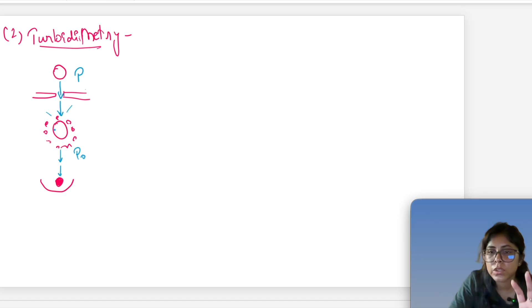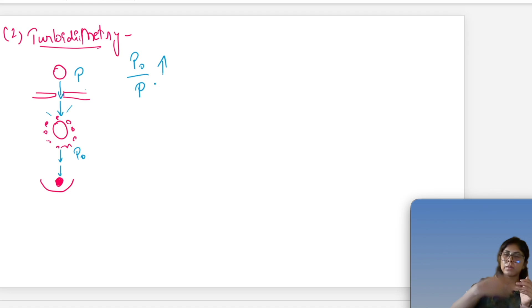If more light is coming out, that means P naught will be high. For example, if most of the incident light comes out, that is P naught. It was not absorbed or scattered by any particle, the light came directly. So if P naught is more, we can say that there are fewer suspended particles. That's why most of the light came out, right? That means turbidity is low. So in nephelometry, if P naught upon P is high, turbidity is high. But in turbidimetry, if P naught upon P is high, that means turbidity is low, right? So this is how turbidity is measured in this turbidimetry process.